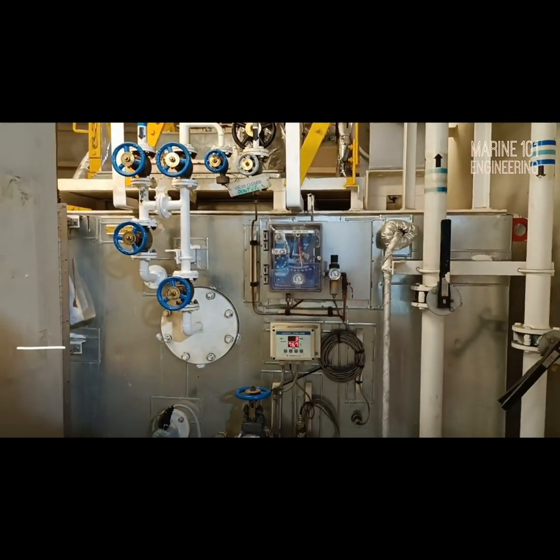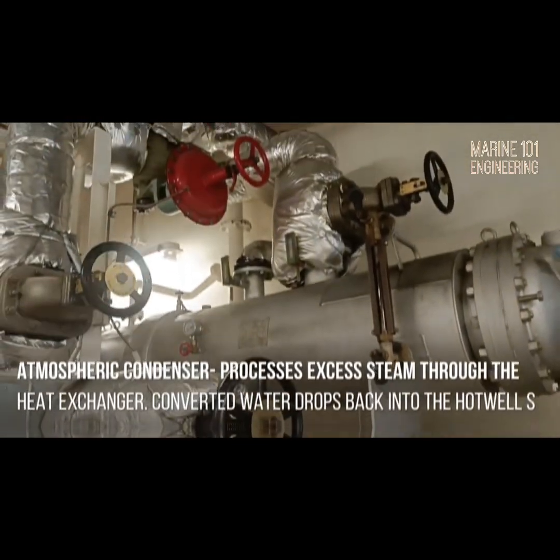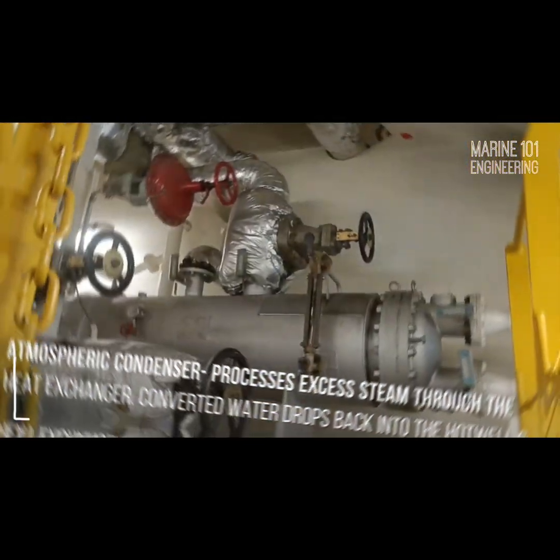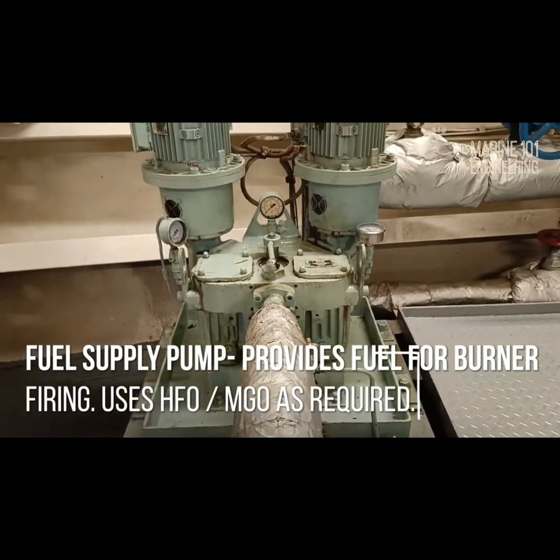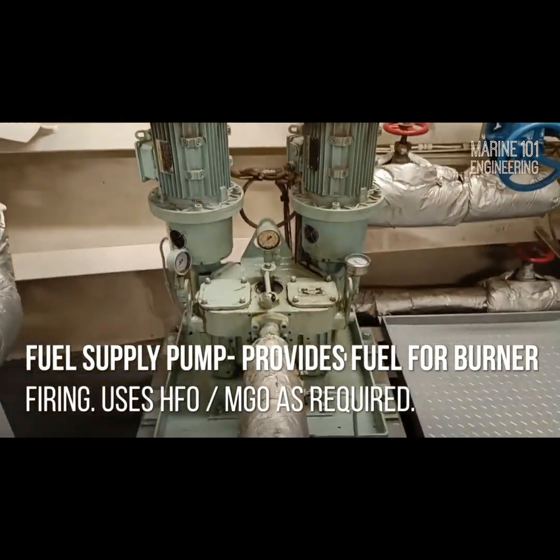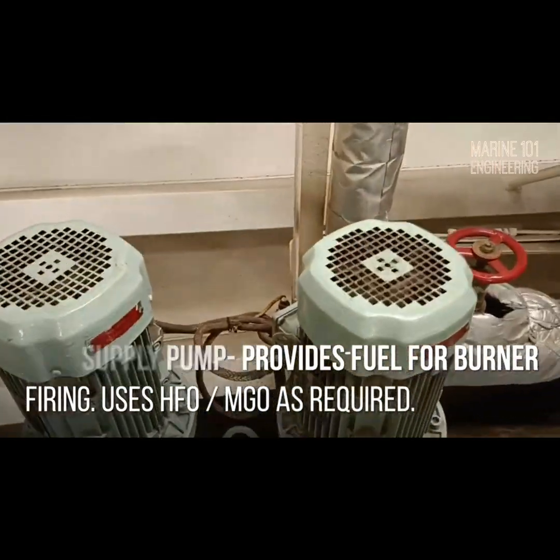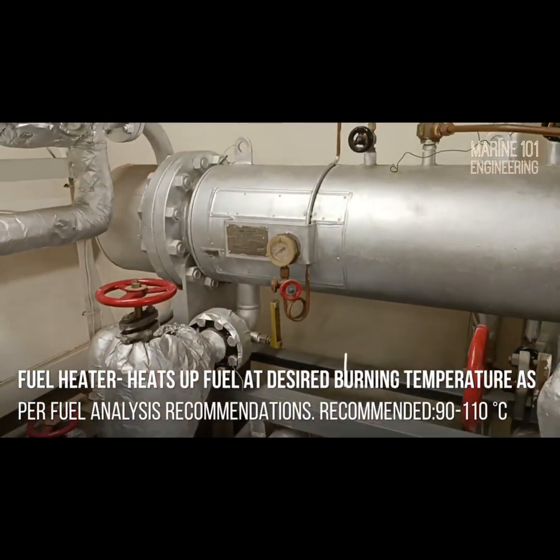Next, the atmospheric condenser unit processes excess and returns steam from the system. The heat exchanger is cooled by seawater and condensates are led back into the system. Fuel supply pumps deliver fuel into the burner for combustion. The system can work with HFO or MGO requirements.